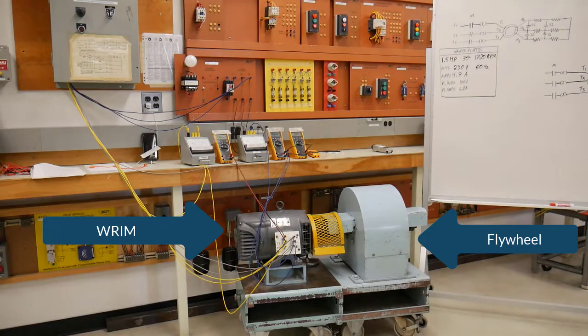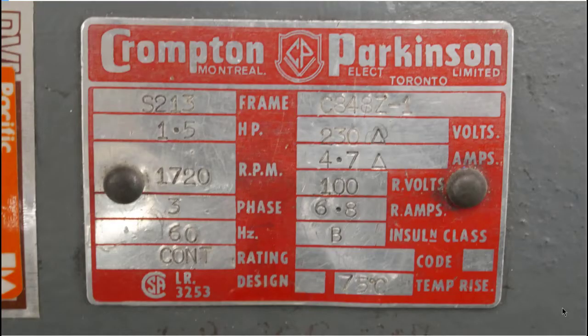Let's look at the nameplate. This wound rotor machine is 1.5 horsepower, 1720 full load RPM, three-phase 60 hertz. It operates at a line voltage of 230 volts. The stator windings are delta connected internally with a maximum line current of 4.7 amps. Maximum rotor voltage is 100 volts and maximum rotor current is 6.8 amps. It's a Crompton Parkinson.